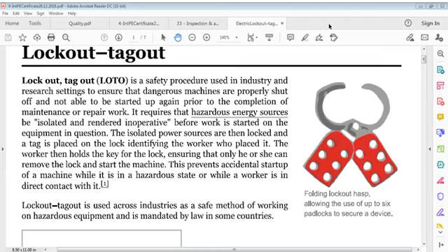It requires that hazardous energy sources be isolated and rendered inoperative before work is started on the equipment in question. Isolated power sources are then locked, and a tag is placed on the lock identifying the worker who placed it. The worker then holds the key for the lock, ensuring that only that person can remove the lock and start the machine. This prevents accidental startup of a machine while it is in a hazardous state or while a worker is in direct contact with it.